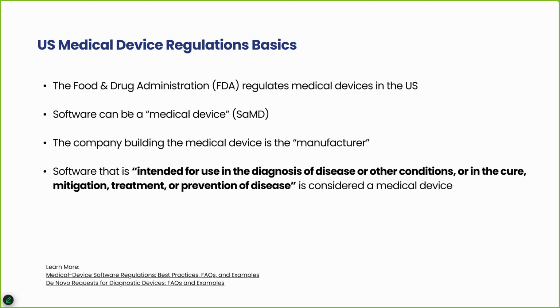So usually the first regulatory question when you have a software product is, is this a medical device? A lot of the times it's very obvious if it is, but there is some nuance to this. For example, there's a category of software called non-device MDDS, where you're just moving images around, that was deregulated and is no longer considered a medical device.